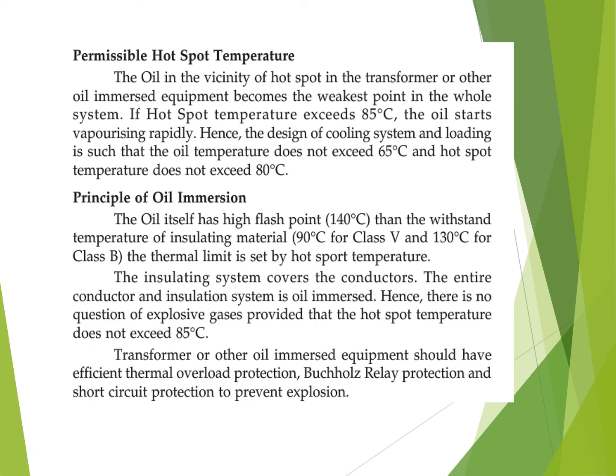Then the permissible hot spot temperature. The oil in the vicinity of the hotspot in the transformer or other oil immersed equipment becomes the weakest point in the whole system. If the hotspot temperature exceeds 85 degrees Celsius, the oil starts vaporizing rapidly. So the principle of oil immersion is that the oil itself has a flash point of 140 degrees Celsius, so it can withstand the temperature of the insulating material. The insulating system covers the conductors and the entire conductor insulation. All these things are oil immersed, so that problems can be avoided.